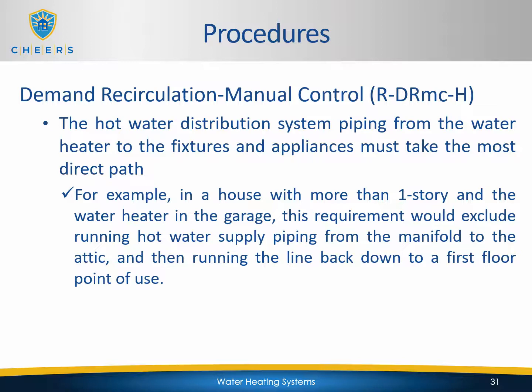The hot water distribution system piping from the water heater to the fixtures and appliances must take the most direct path. And again, for example, in a house with more than one story and the water heater in the garage, this requirement would exclude running hot water supply piping from the manifold to the attic and then running the line back down to a first floor point of use, just like we talked about in other distribution systems.